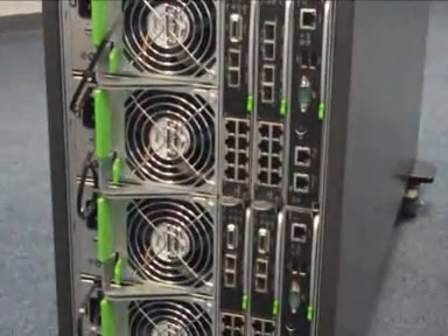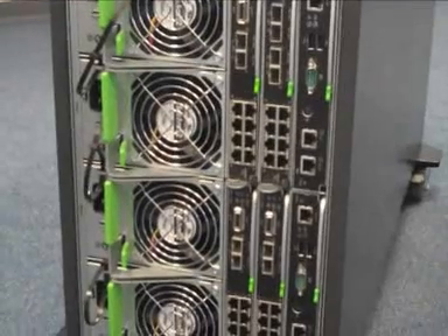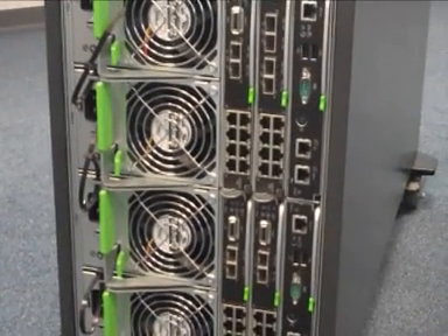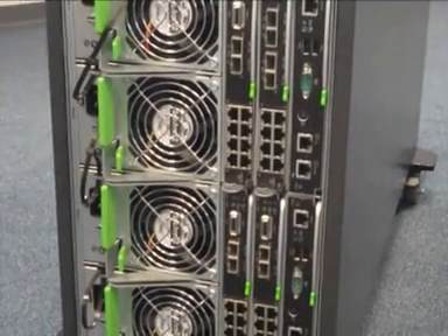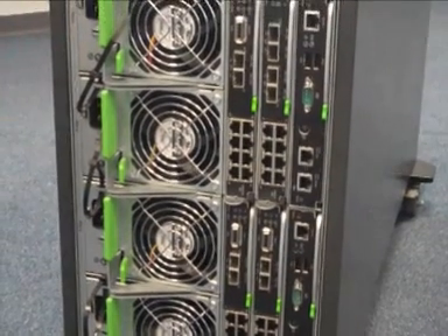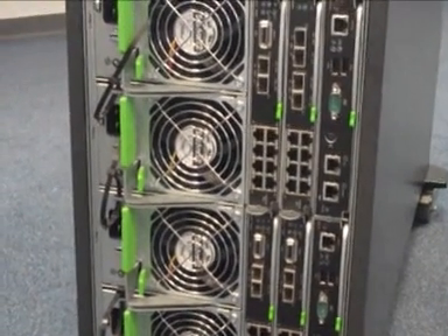Okay, on the rear side on the BX400, we have the PSUs, the power supply modules. So basically we do have 4 power supplies. Each of them is running with 1600 watts, but in a complete redundant mode. That means 2 of them enabled are enough to run the whole box.